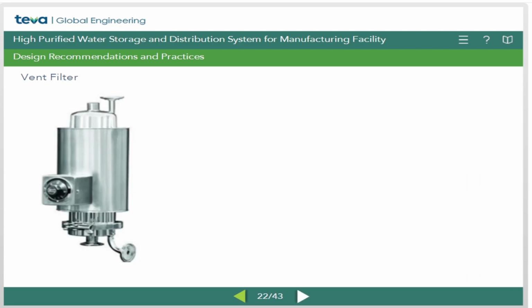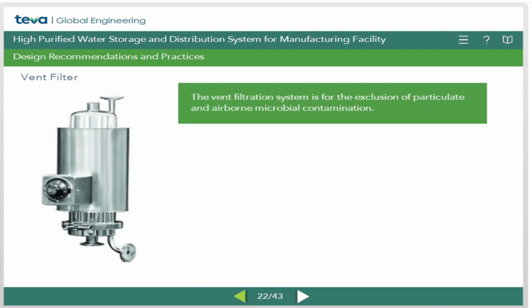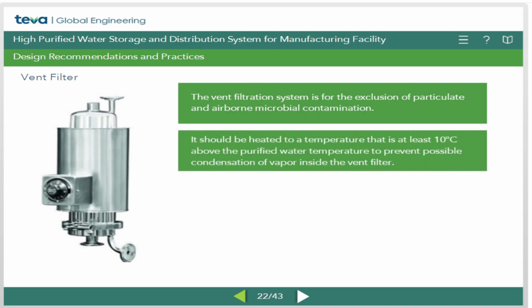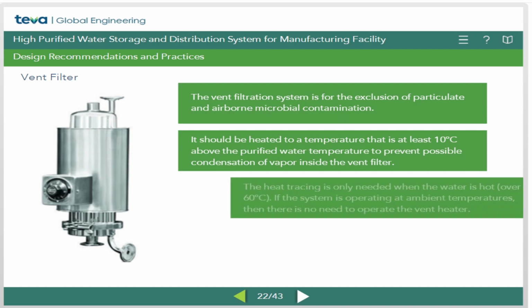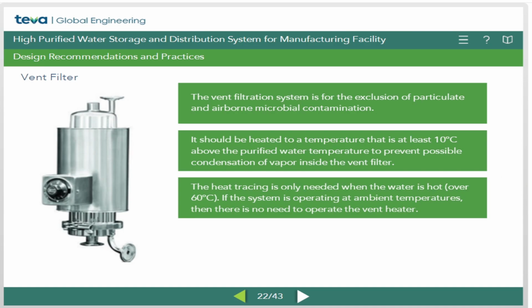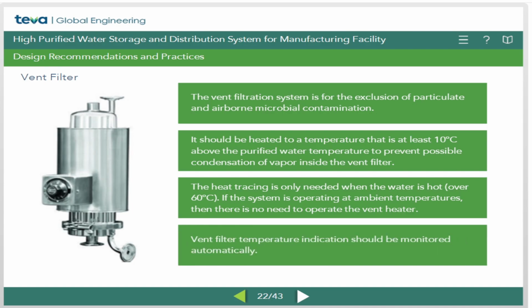Next, we look at vent filter. The vent filtration system is for the exclusion of particulate and airborne microbial contamination. It should be heated to a temperature that is at least 10 degrees centigrade above the purified water temperature to prevent possible condensation of vapor inside the vent filter. The heat tracing is only needed when the water is hot. If the system is operating at ambient temperatures, then there is no need to operate the vent heater. Vent filter temperature indication should be monitored automatically.